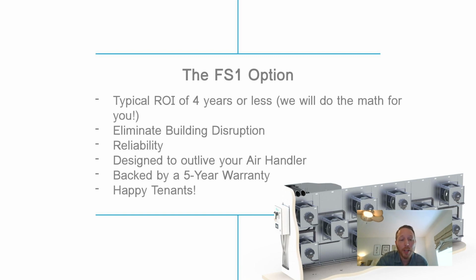And look, it's plug and play. We have our patented Quick Connect box. Our system comes with harnesses that you snap onto the bulkhead wall, so you just can't get it wrong. You do have to connect power and an 8-conductor control cable between the Quick Connect box and our control panel, and that's it. If your BMS goes down, or you have power issues, we've got everything backed up with fuses. If your BMS goes down, you walk up to it, you put it in hand mode, and it bypasses your BMS and our controller and everything, and it'll run until you get your control side fixed.